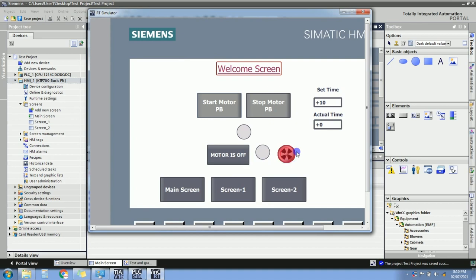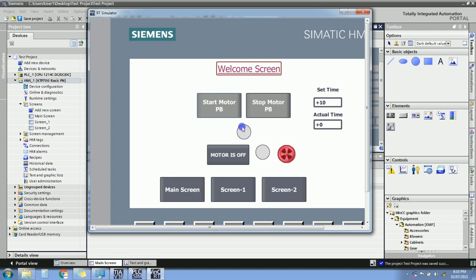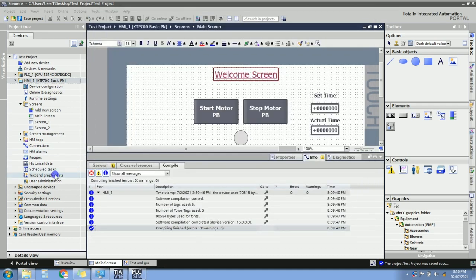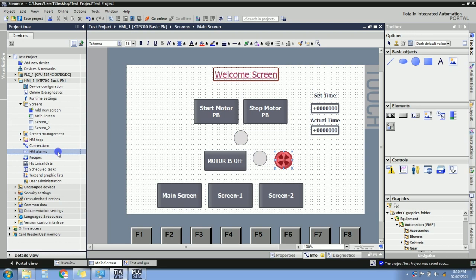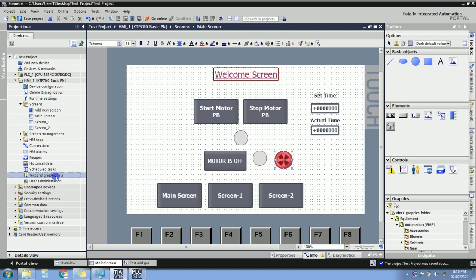For HMI alarms I have a separate video - the link is in the description. For recipe I also have a separate video. For user administration, I've already uploaded a video. Today we have seen text list and graphics list. Let's look at some more controls - on the second screen you can add a bar graph. Take a bar graph from the toolbox, set maximum scale to 10 and minimum to 0, and assign the timer actual time tag.